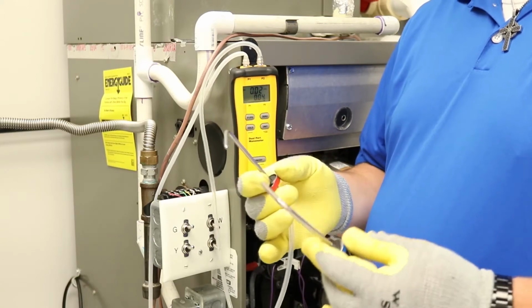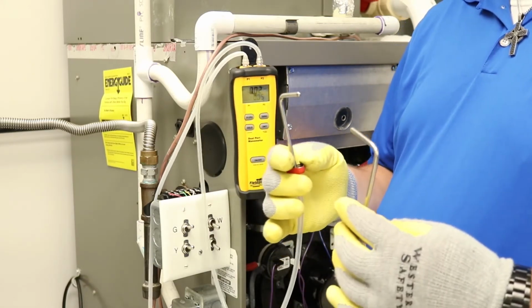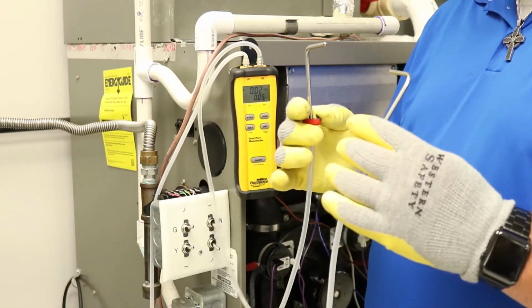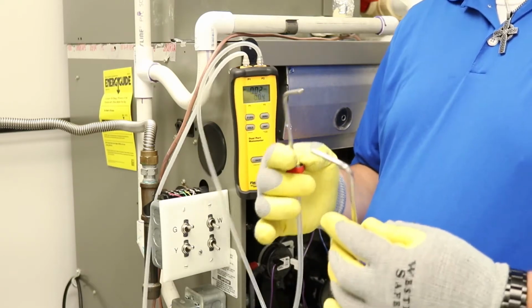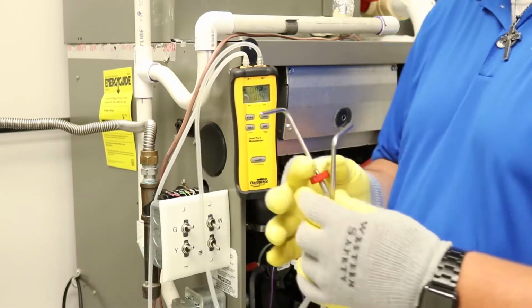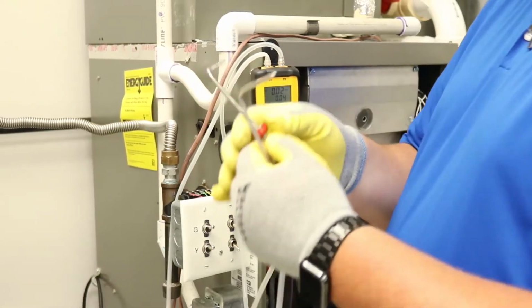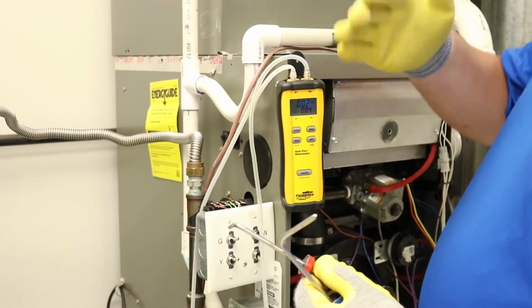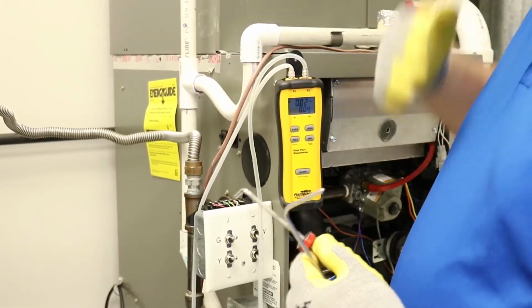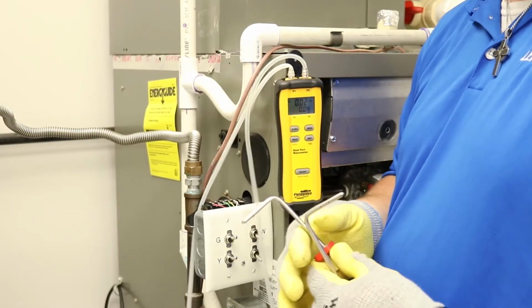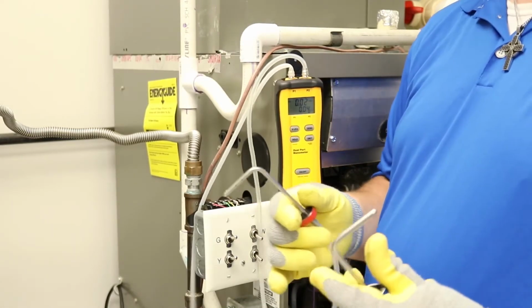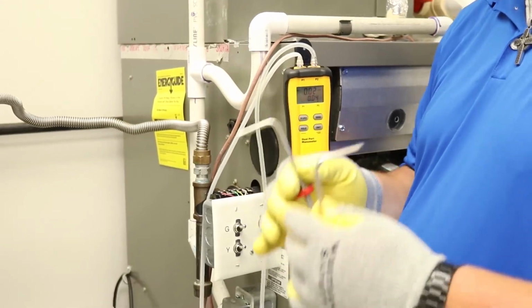Again, that's something that is going to be paramount in determining that you have the right static pressure for the system. A lot of technicians will want to install these to where one's on the opposite side of the evaporator coil and one's on the other side of the air filter. That's not the proper way to check static pressure. You want to keep it inside the box.